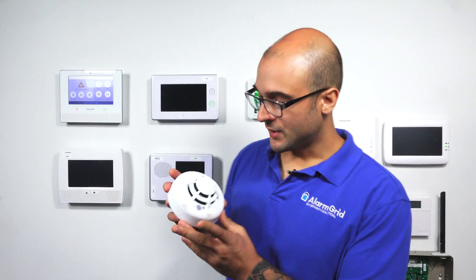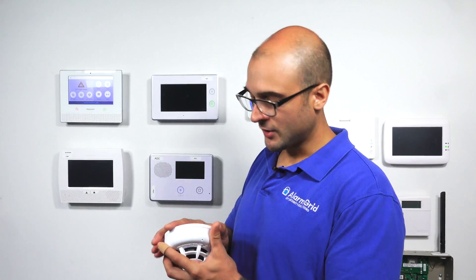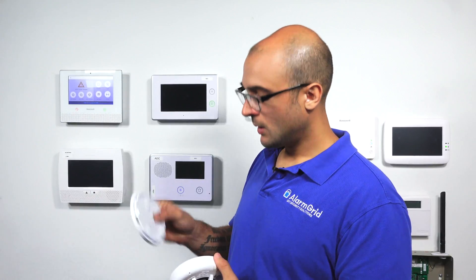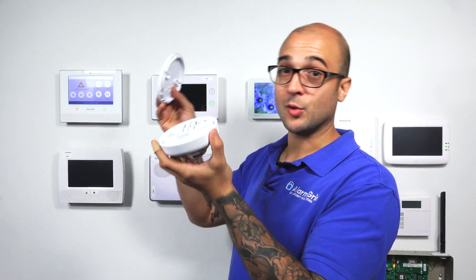Another option you have with the system is to use wireless smokes. The GC3 system is compatible with 2GIG sensors and also compatible with Honeywell 5800 sensors, which gives you quite a few different options. This right here is the SMKT3-345. This is a 2GIG smoke detector, heat detector, and freeze detector — programs wirelessly right into the system, and it works great. These are easy to install; you just pop off its back base, it has little screw holes, install it on the ceiling, pop it on, turn it on, program it in, and you're good to go.